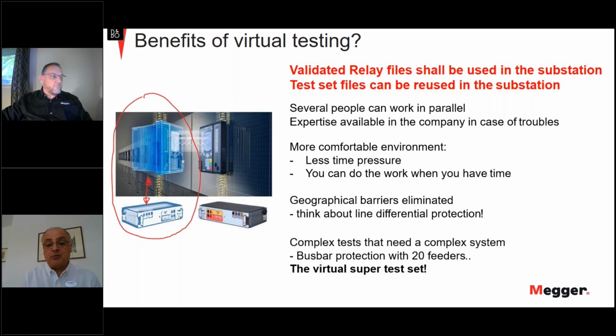And also complex tests, because we can have a virtual super test set that can have 20 feeders with the 60 currents, which doesn't exist in reality, even if we can daisy chain our test sets. And then you can perform some tests that you might not even think to perform in the physical situation.